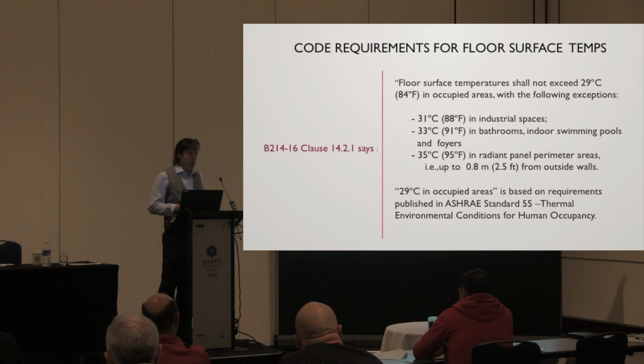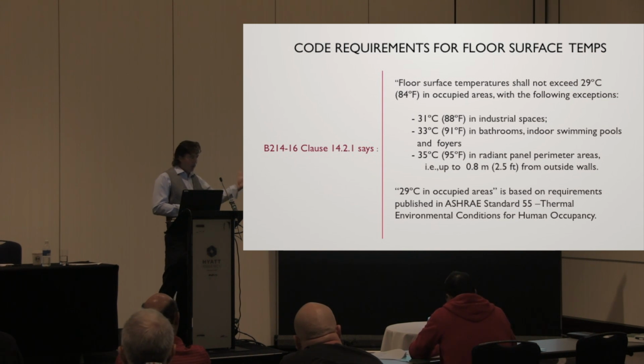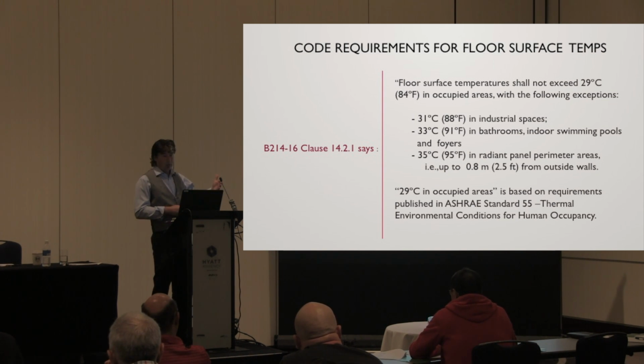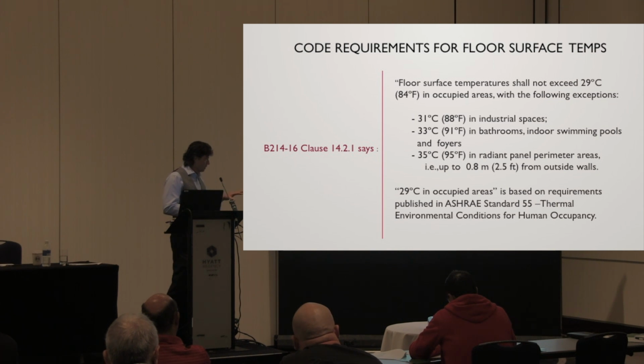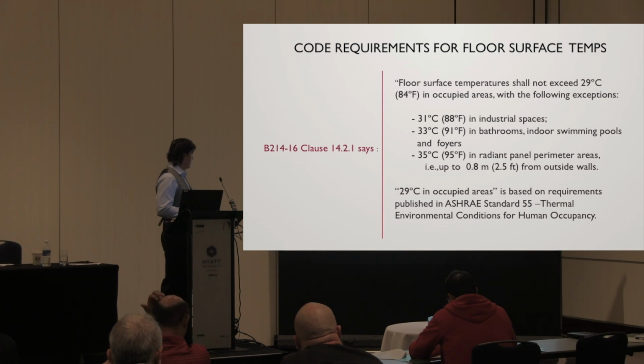Remember I was talking about maybe running a serpentine loop a few times, and that's going to be a lot hotter there. You put your supply water there, and as you work your way in with your tubing, which is going to be maximum 300 feet in length, as it comes in, it's going to cool a lot. So your potential floor temperatures can be quite a bit higher there, but CSA is okay with it. So 95 there, up to 2.5 feet from outside walls. So also mentioned in the ASHRAE standard 55. Any questions about that?